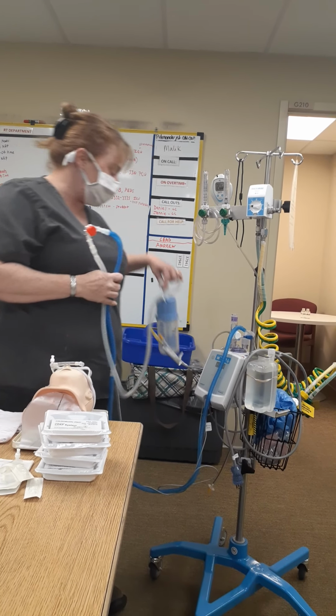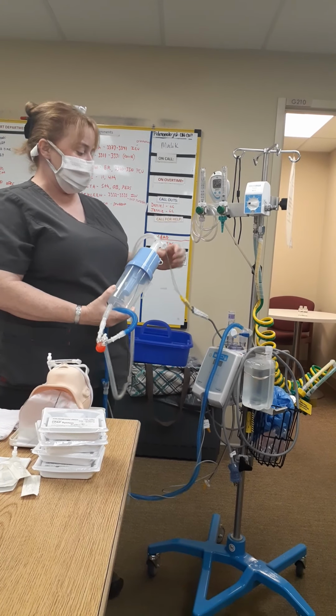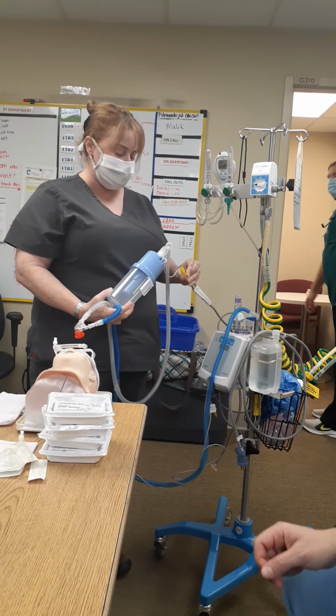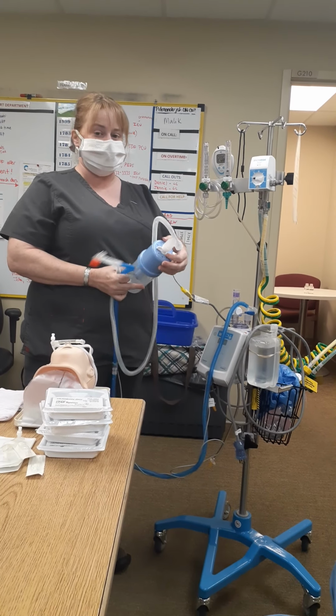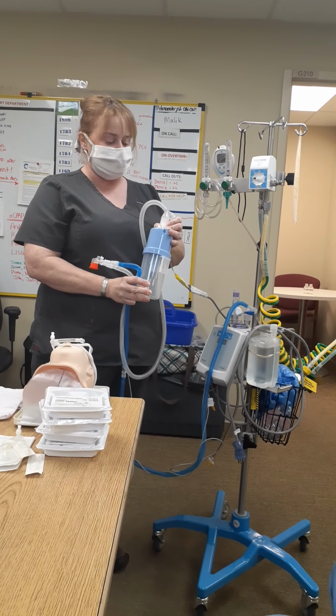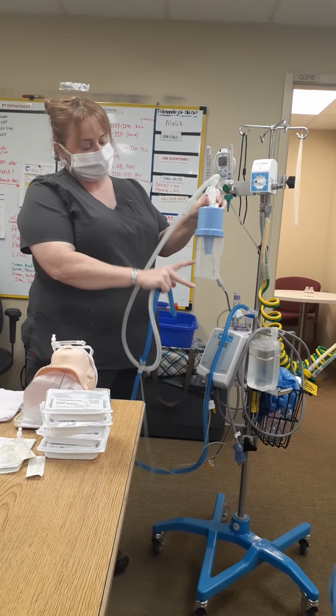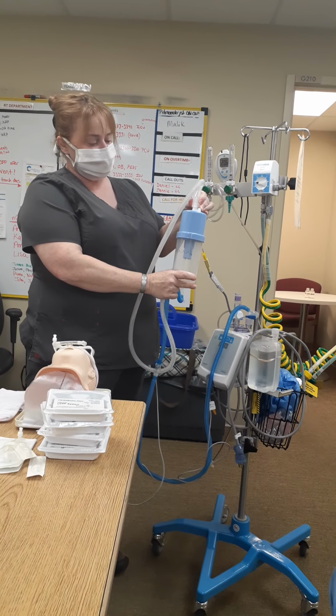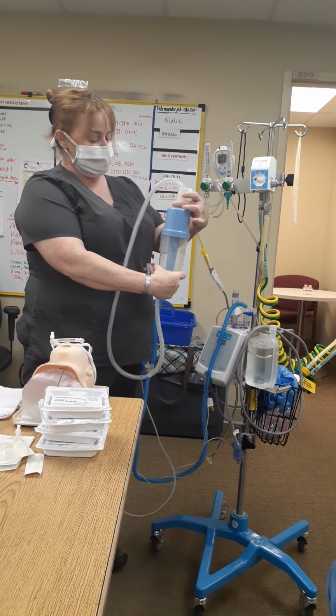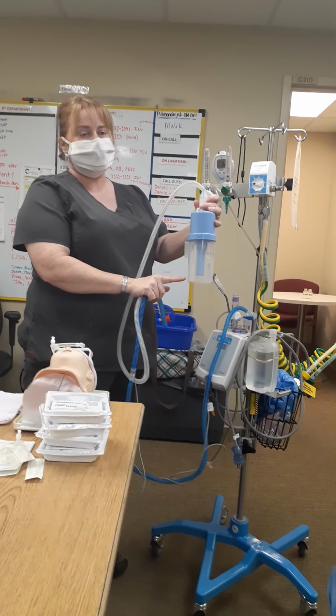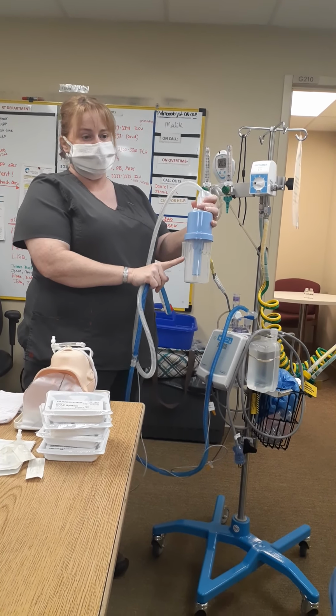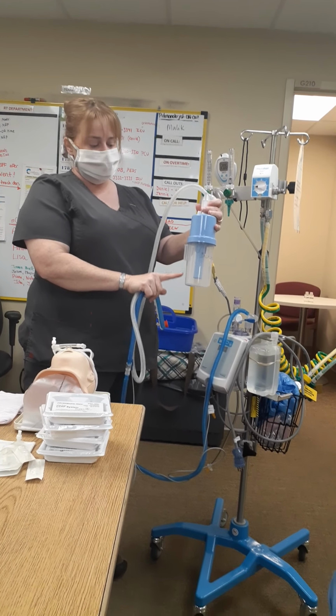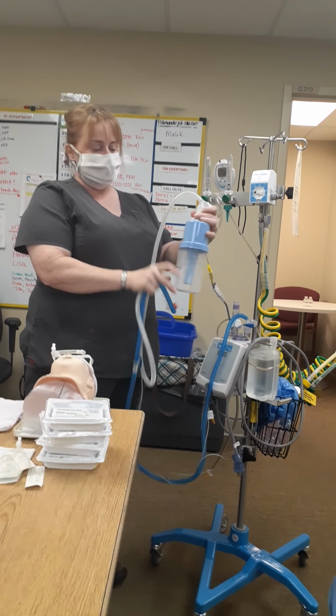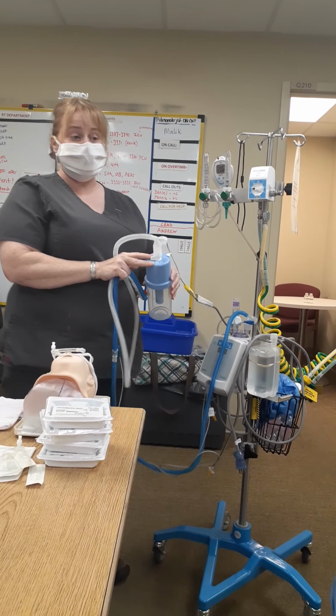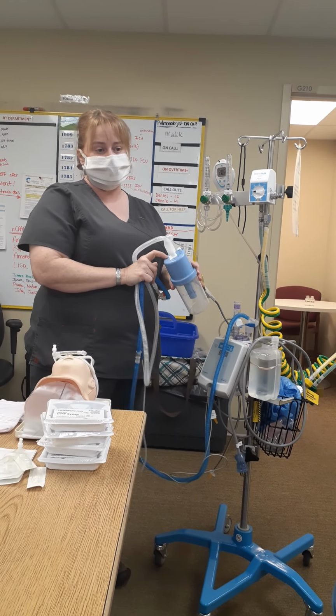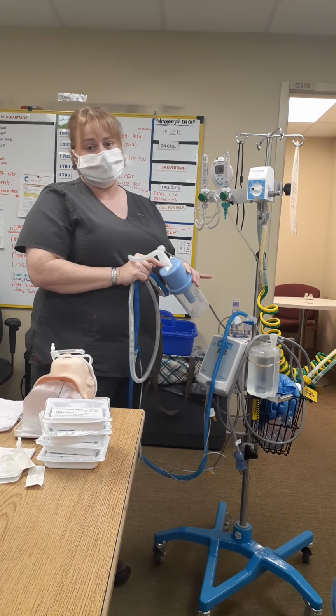I see. Okay, so this is the bubble bottle on the bottom here, and it does have to be plugged into the heater in the yellow cord. The CPAP does have to be set to your level on top of the bottle. As you set your CPAP, so like a level 2, you can see the column is just barely down into the water level. As you advance CPAP 3, 4, 5, 6, 7, 8, the column goes down farther in. So this is just to kind of show you in your mind that a CPAP of 8 is going to take a lot more force, a lot more pressure to overcome that back pressure. And we will always start out on 5, CPAP of 5, but we can advance to 6 or 7. If we have a baby that's on 8, we're going to prepare to intubate that baby.